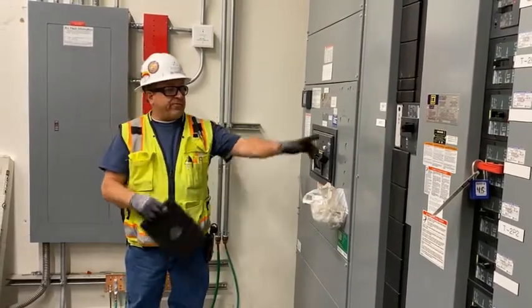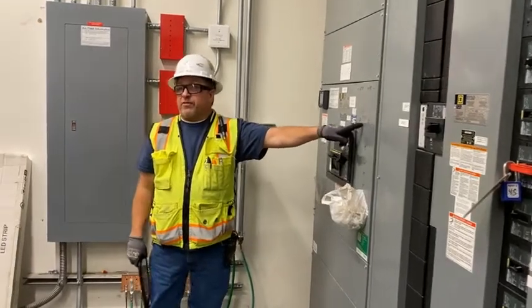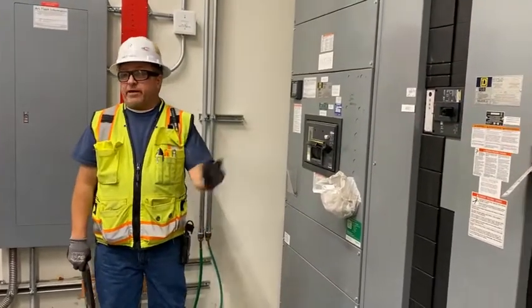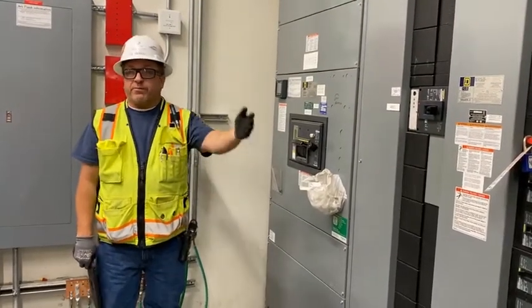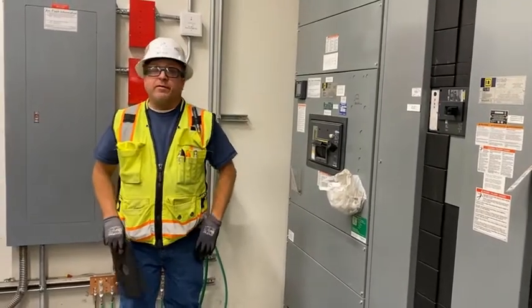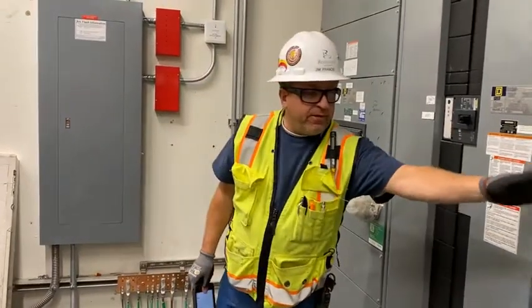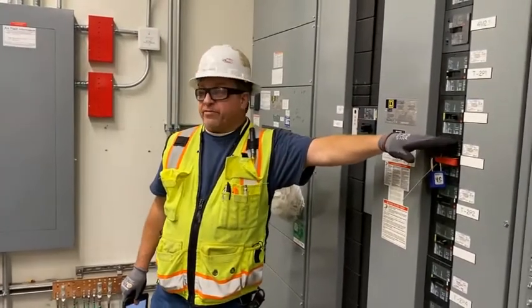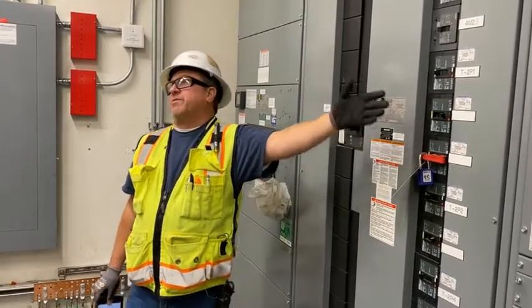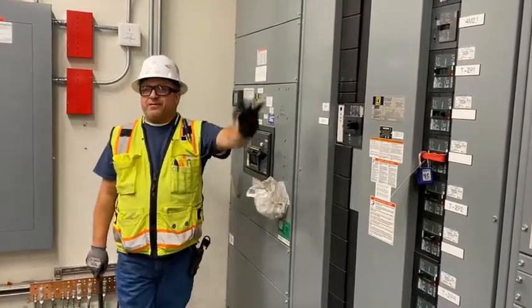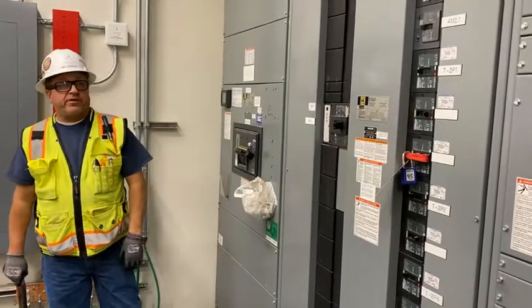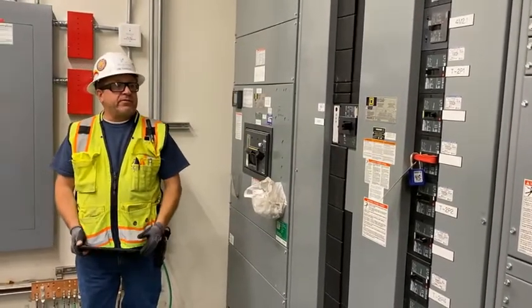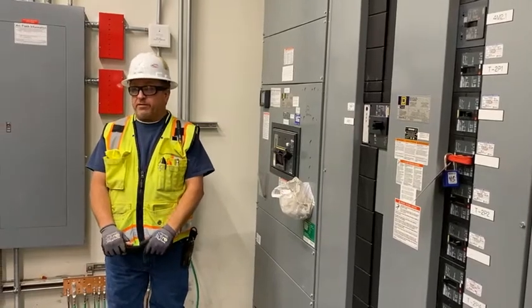Yes, and the phase rotation for this project is counterclockwise. That is what we got from the utility, so we matched it. So if you ever open this up and you notice that on the high side of this breaker we have yellow, don't say those guys must not know what they're doing - that's just the way Square D gear is. They're the only ones I know that are like that.